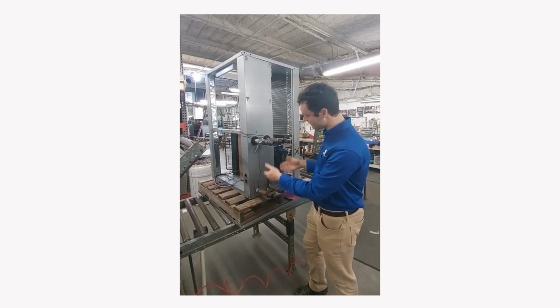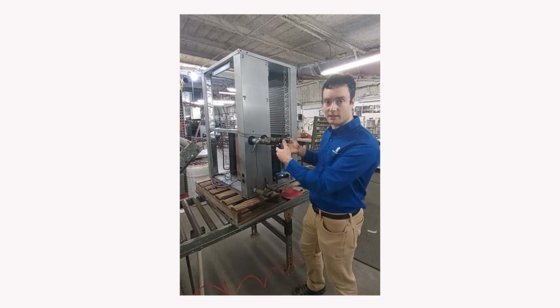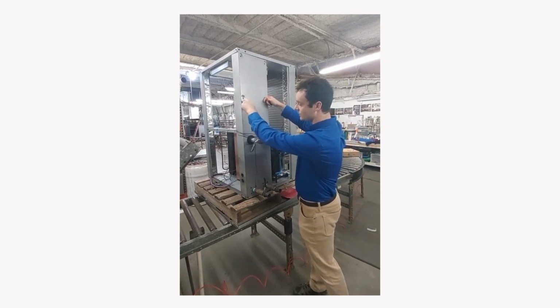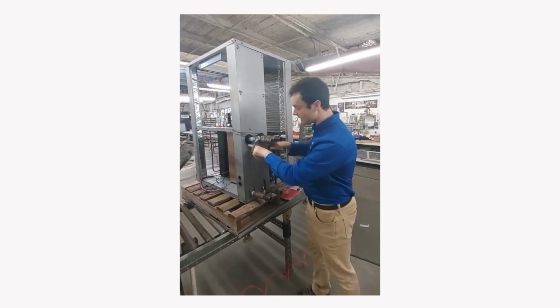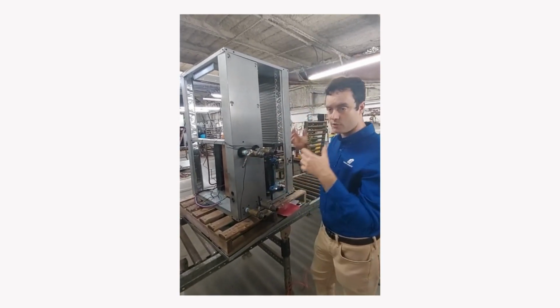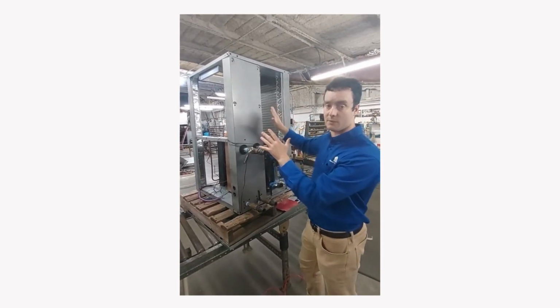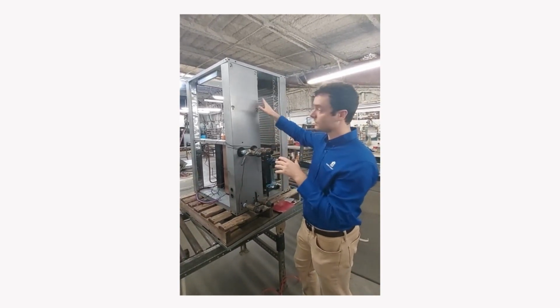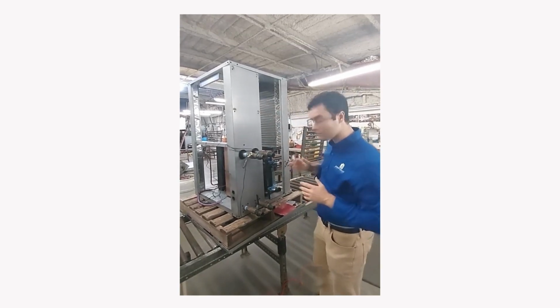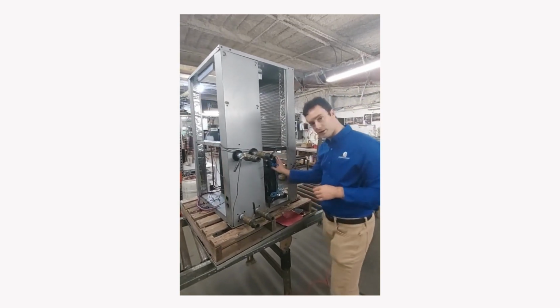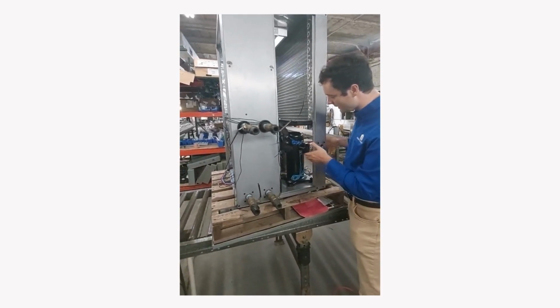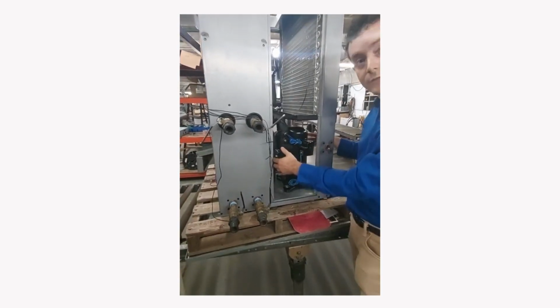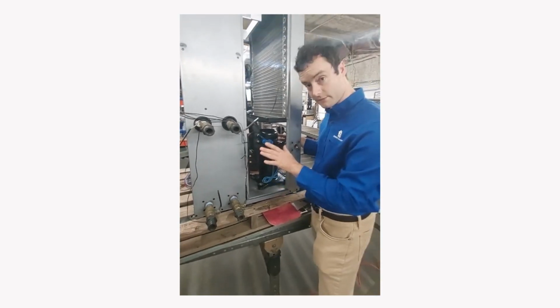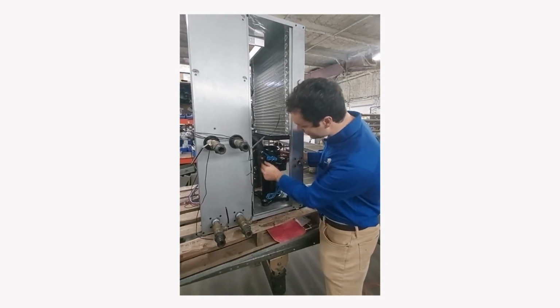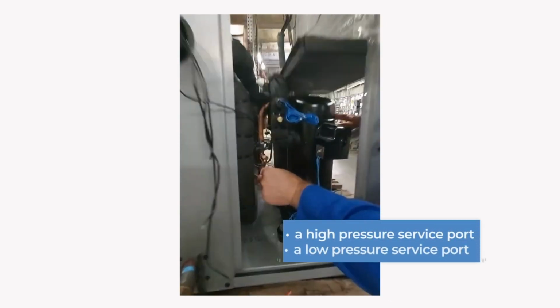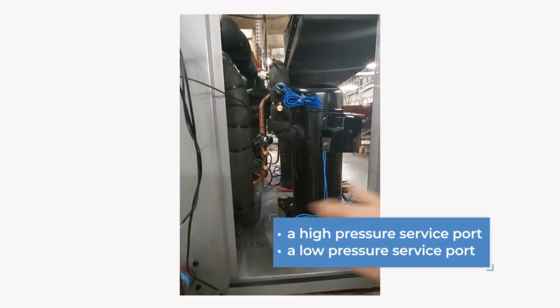Here we just have temporary ports for testing and pressure testing, things like that. But these will actually be pre-piped and plumbed, so that they go directly in, and as soon as you bring it down, your ground loop is almost already installed. You just need to connect your heat pump directly to the ground loop. A couple of other little features that I just want to show you. You can see the compressors right here. We have dedicated this whole little space right here for easy compressor removal. That's definitely intentional. We also have our service ports right here. So we have a high pressure and a low pressure service port that are very accessible.